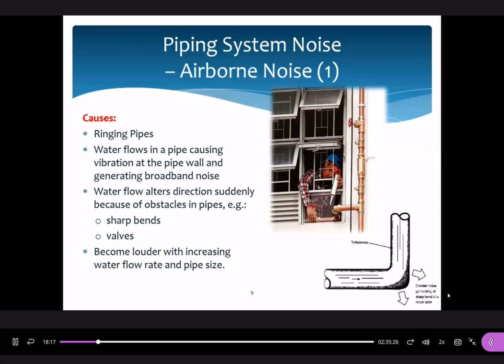They proposed a number of control remedies. The first is to use a larger radius, so you can minimize the vibration effects. The second is the use of rigid mounting, to prevent vibration effects generated from the water flow. The third is to use a larger pipe or adjust water flow velocities to below 2 meters per second to reduce the water flow velocity.